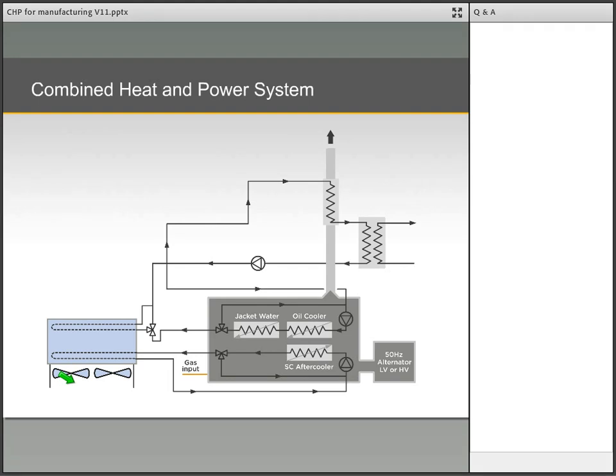The jacket water circuit comprises a water pump, an oil cooler, which is a shell and tube oil cooler usually fixed to and part of the engine, and the engine water jacket circulating around cylinder liners and cylinder heads, plus a three-way valve to ensure optimum operating temperature. The coolant in this circuit recovers heat from the engine and also traditionally from a shell and tube heat exchanger placed in the exhaust gas stream, with the gas going through the tubes and the water flowing around the outside of them.